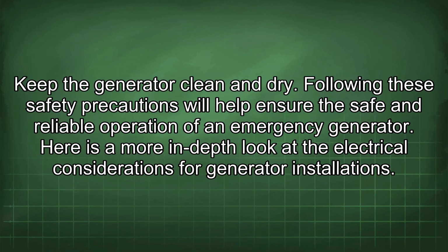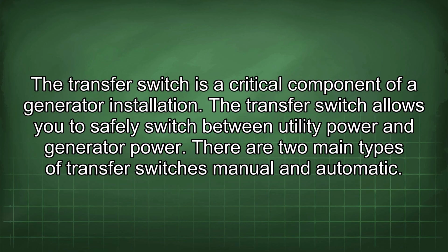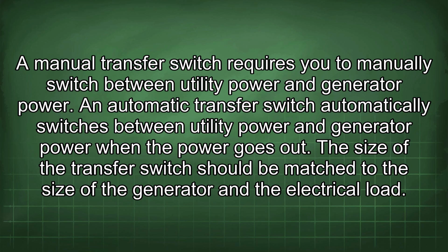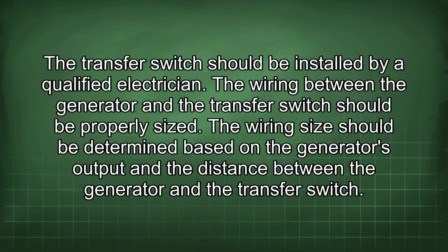Here is a more in-depth look at the electrical considerations for generator installations. The transfer switch is a critical component of a generator installation. The transfer switch allows you to safely switch between utility power and generator power. There are two main types of transfer switches: manual and automatic. A manual transfer switch requires you to manually switch between utility power and generator power. An automatic transfer switch automatically switches between utility power and generator power when the power goes out. The size of the transfer switch should be matched to the size of the generator and the electrical load. The transfer switch should be installed by a qualified electrician.